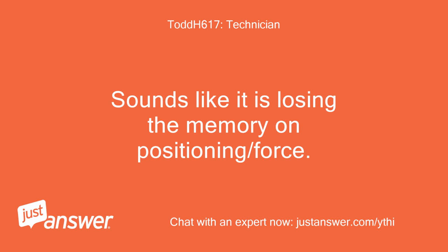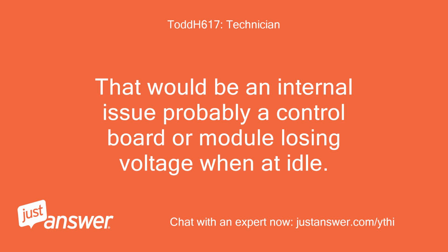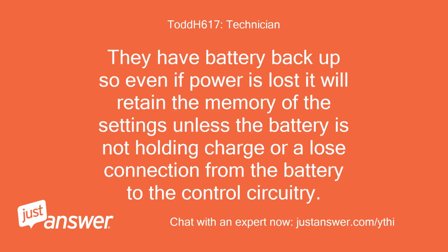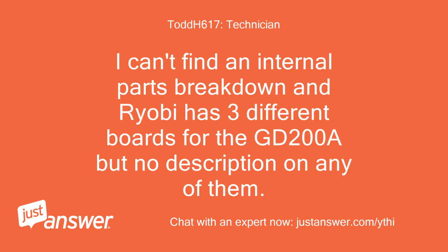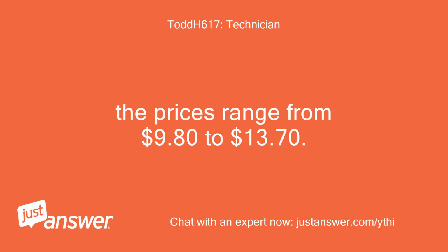Sounds like it is losing the memory on positioning and force. That would be an internal issue, probably a control board or module losing voltage when at idle. They have a battery backup, so even if power is lost it will retain the memory of settings, unless the battery isn't holding a charge or there's a loose connection from the battery to the control circuitry. I can't find an internal parts breakdown, and Ryobi has 3 different boards for the GD200A but no description of any of them. The prices range from $9.80 to $13.70.